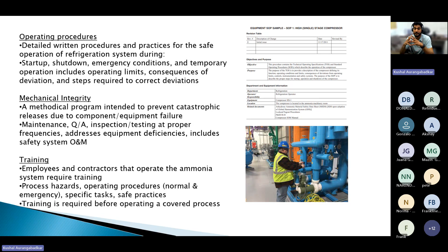Crucially, training must be completed before personnel are authorized to work on the system or covered processes. So training is not just a box to check—it really needs to be performed and verified to make sure the individual is fully trained and capable of performing the associated task. When you combine these three pillars of operating procedures, mechanical integrity, and training, it forms the operational core of a safe and effective ammonia refrigeration system.